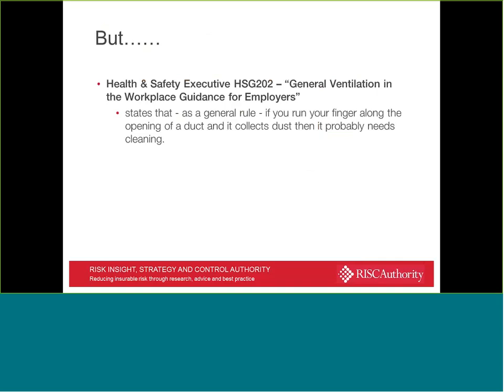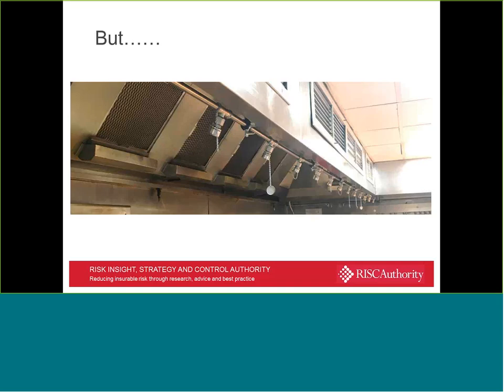As I mentioned earlier, the HSG 202 says, as a general rule, if you run your finger along the opening of a duct and it collects dust or grease in this instance, then it probably needs cleaning. It's as straightforward as that. And we could draw correlations to depths of dust and dirt in terms of minimising dust explosions in dusty environments, but grease responds fairly differently and doesn't necessarily fall into a similar category. But we'll talk about how that's measured itself.